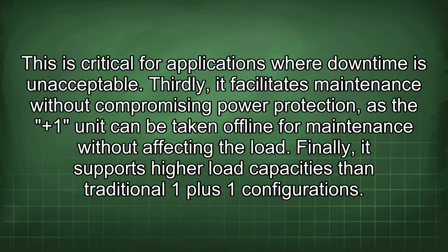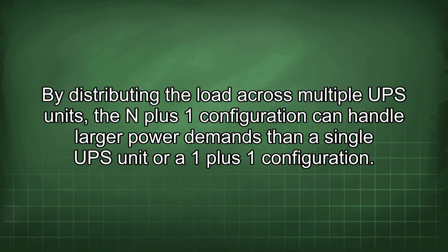Thirdly, it facilitates maintenance without compromising power protection, as the +1 unit can be taken offline for maintenance without affecting the load. Finally, it supports higher load capacities than traditional 1+1 configurations. By distributing the load across multiple UPS units, the N+1 configuration can handle larger power demands than a single UPS unit or a 1+1 configuration.